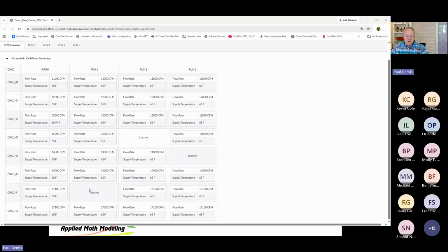Sometimes they fail. You have to understand that they will at some point need to go down and be replaced. And you need to understand if your worst case loads will hold up in that situation. And then over here, I shut off a different one. I shut off one at 15,000, then over here, one at 14,000.